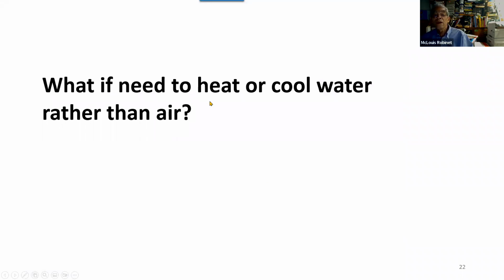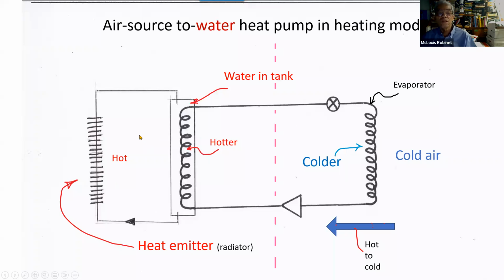So we've been talking about heating air. What if you needed to heat or cool water? The systems we've been using, we'd call air source to air heat pumps, but you could have an air source to water heat pump, where inside, instead of just having a fan blowing over this hot coil to heat the air, you could instead heat the water and connect this to a radiator or something. That would be called an air source to water heat pump. The concept still applies, removing heat from hot to cold.